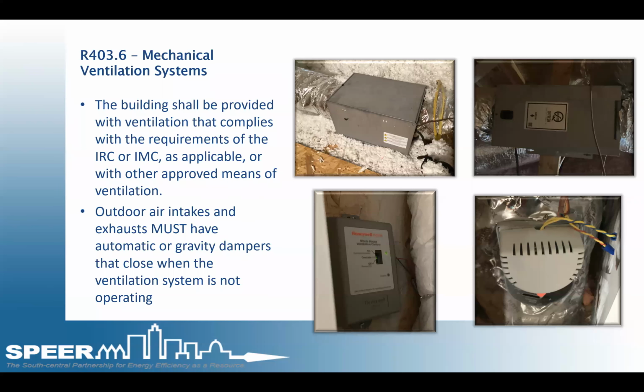There are a variety of mechanical ventilation systems, also known as fresh air systems, ranging from tie-in systems that use the air handler as the fan system to standalone systems that use far less energy for the same amount of air. Due to the increased energy use, using the air handler as the fan usually fails energy modeling and a standalone fan must be used, due to the fact that the air handler uses such a high watt draw and energy usage. It is not allowed in the energy model and must resort to a smaller fan unit.